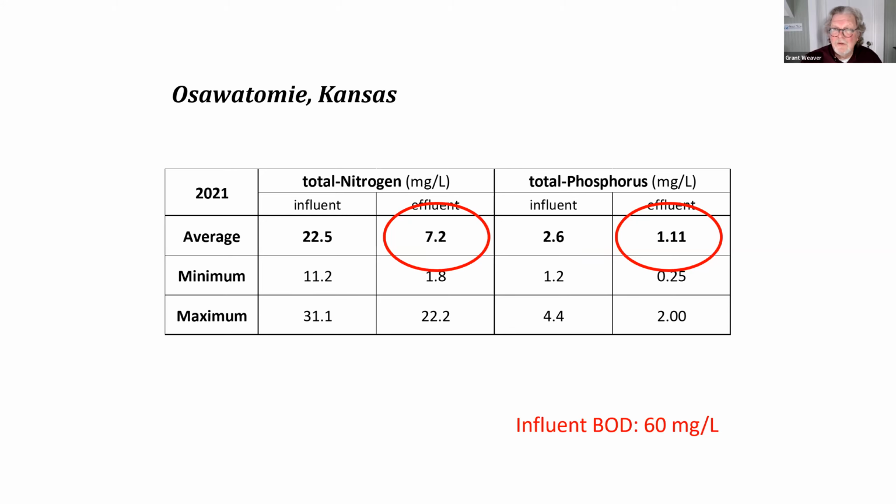Here's like the questionnaire. So low BOD, low influent nitrogen, okay. A percentage of that influent nitrogen is going into building cells. If there was a higher BOD, I'm sure that this number could be driven lower. But a goodly percentage of that drop from influent nitrogen of 20 to 7 is just going into building new cells that goes out as waste sludge.